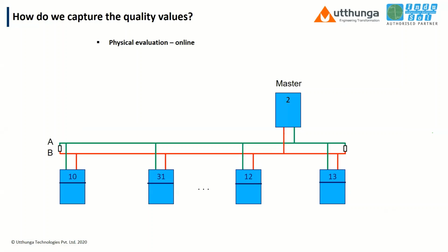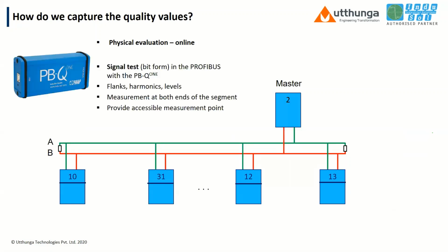Even though we pinpoint the error, we need to know what is the PROFIBUS voltage, right? What is the PROFIBUS voltage in each node? So for that, we have the PB-Q ONE. PB-Q ONE is a signal quality tester. It's a measuring and diagnostic tool, especially for commissioning, factory acceptance test, maintenance and services, and moreover also troubleshooting in PROFIBUS lines.